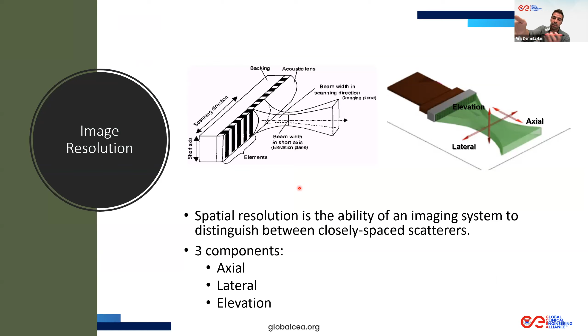Let's start with the axial. The resolution of the axial is limited to half the wavelength. Why is that? Because if we have two scatterers, as you can see here, if their distance is higher than half the wavelength, I will have two discrete echoes coming back. So I will be able to print two different lines. So I will see two different structures. But if they were closer than half the wavelength, then this echo would step on the first one, and I would receive one echo back. So I wouldn't be able to understand that I have two different structures in here.